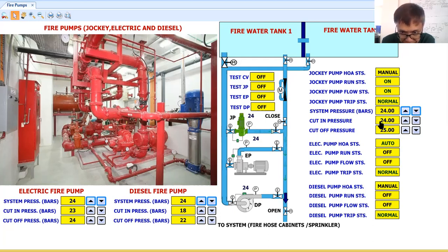So what is happening now? My jockey pump kicks in, okay? So this is simulating that there is a small leak in the system, okay? So the jockey pump will be the one to maintain the system pressure, okay? Now let's say the pressure goes up, okay? So it's already 25. As you can see, the jockey pump should stop. So the purpose of the jockey pump is to maintain the system pressure. For small leaks, the jockey pump will be the one to bring the pressure back to the system pressure.